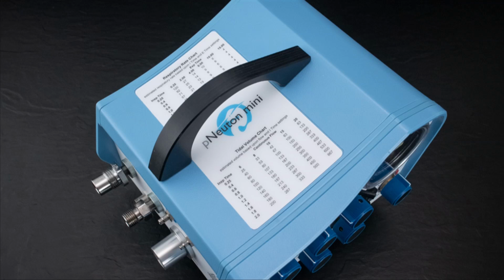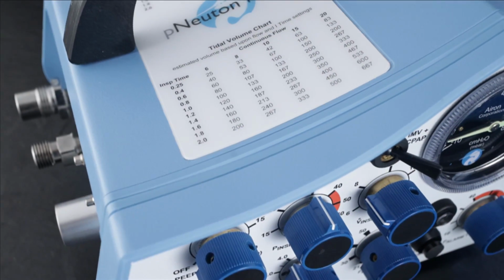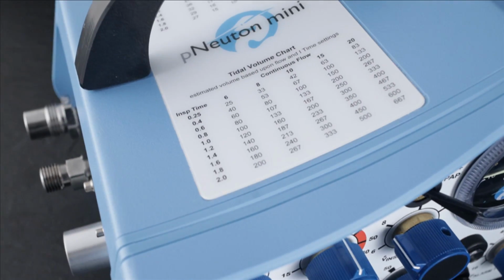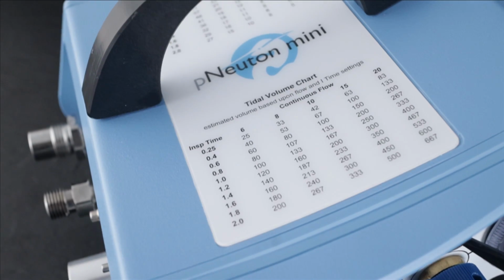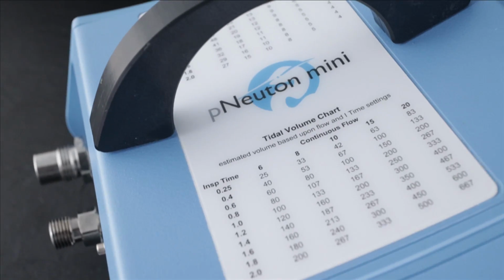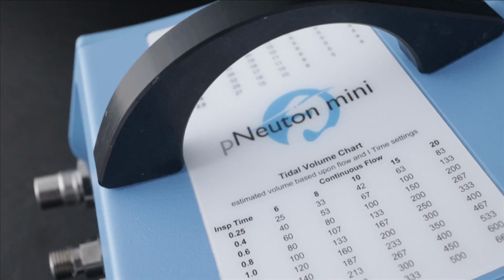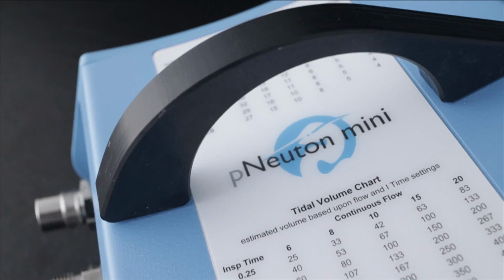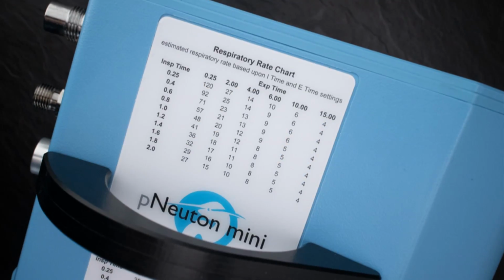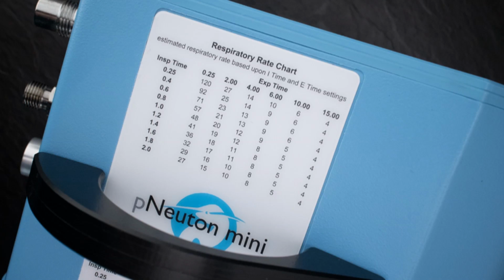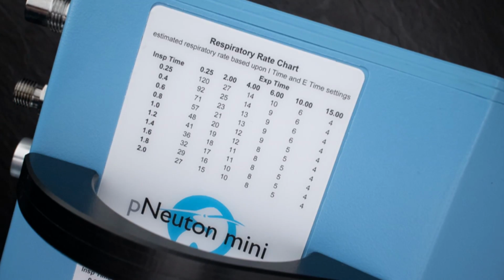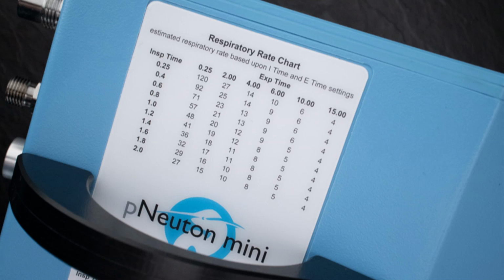For reference, there are 2 charts on the top of the ventilator. One chart shows the maximum tidal volume based on the inspiratory time and the continuous flow. With pressure-limited ventilation, the delivered tidal volumes will be lower. When setting the E time, refer to the respiratory rate chart to estimate the delivered breaths per minute calculated from the I time and the E time controls.